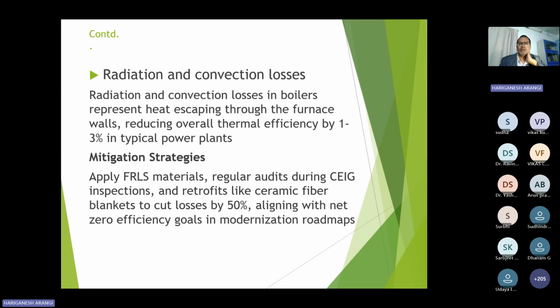And the next loss is the radiation and convection losses. Radiation and convection losses in a boiler represent heat escaping through the furnace walls, reducing overall thermal efficiency by 1 to 3% in power plants. Mitigations: regular auditing, using FRLS materials, and retrofits like ceramic fiber blankets to cut losses by 50%, aligning with net zero efficiency goals. This is towards the modernization of plants.